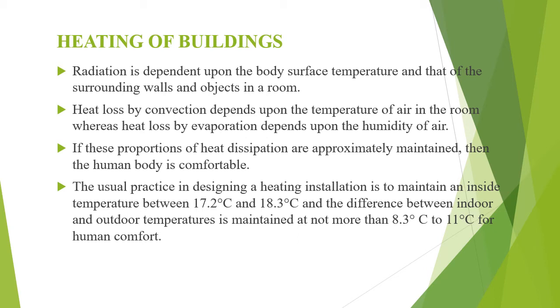The usual practice in designing the heating installation is to maintain an inside temperature between 17.2 degrees Celsius to 18.3 degrees Celsius, and the difference between indoor and outdoor temperatures is to be maintained at 8.3 degrees Celsius to 11 degrees Celsius for human comfort.